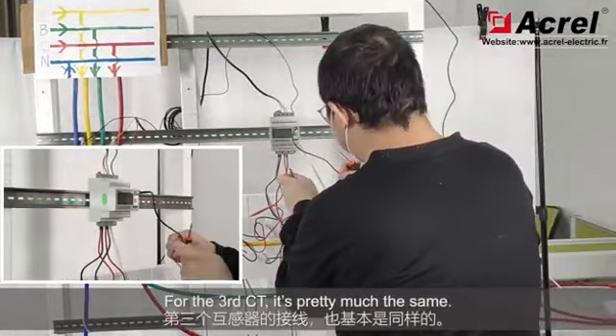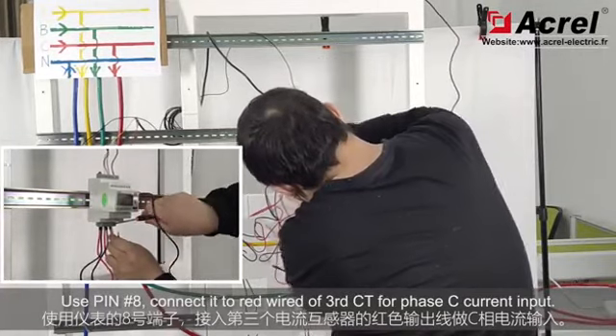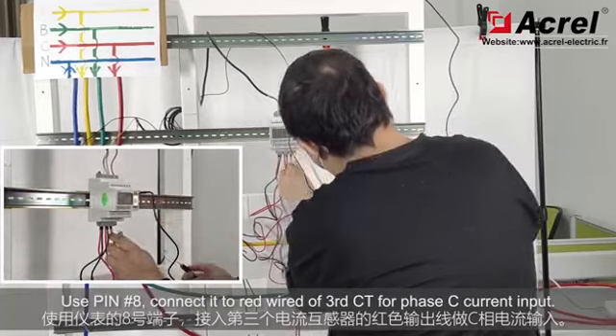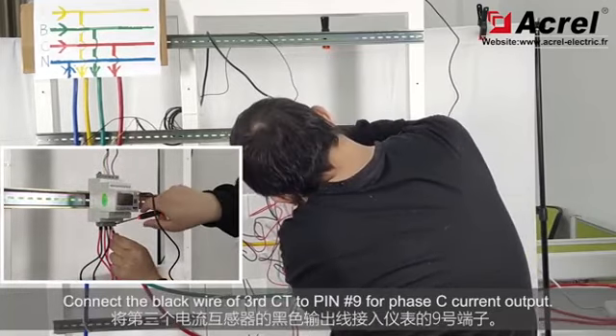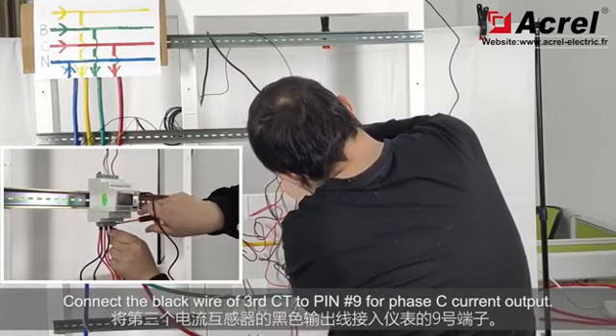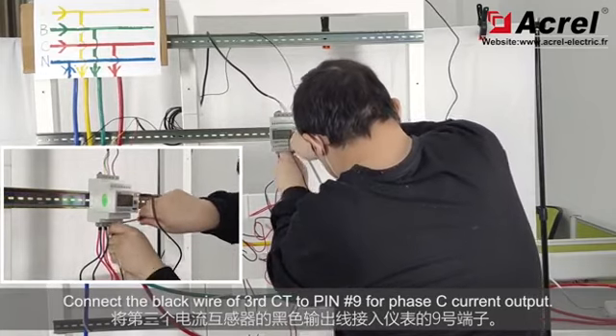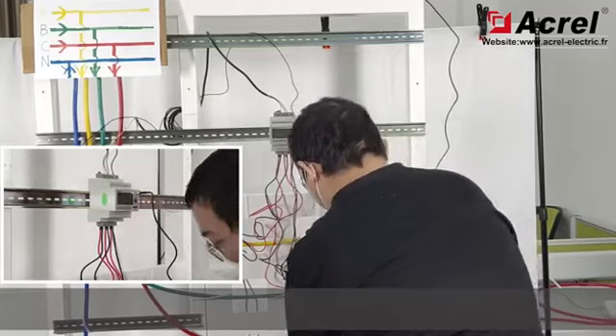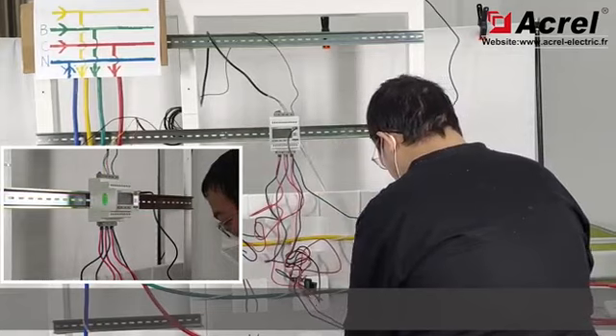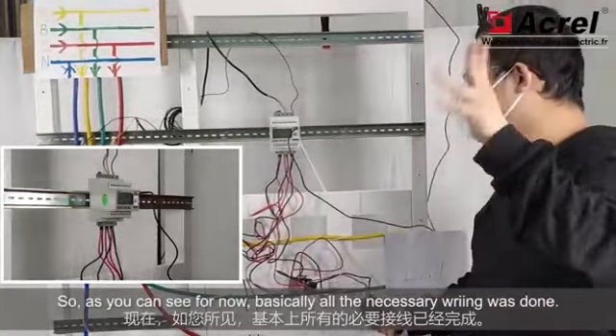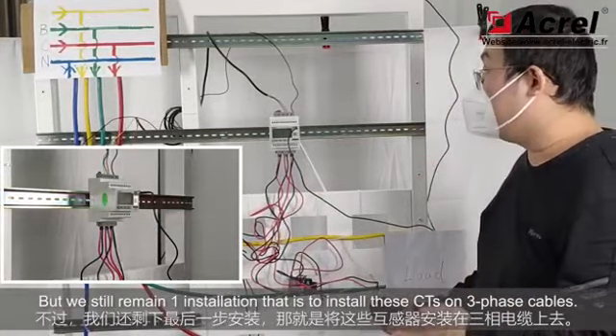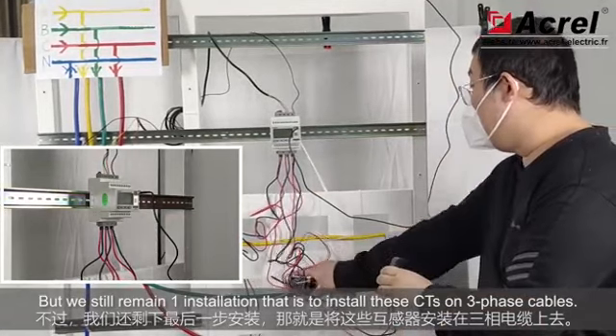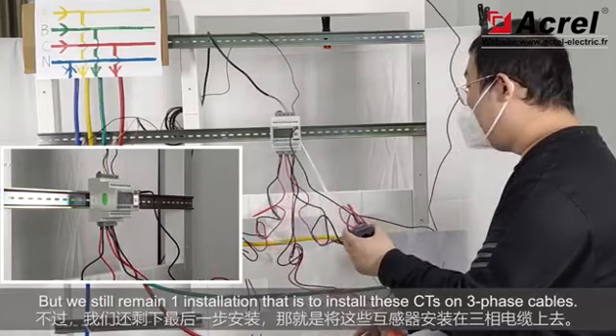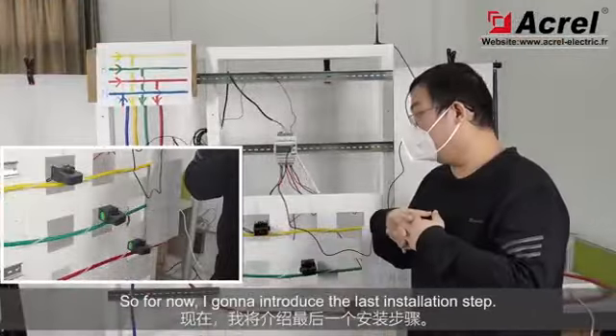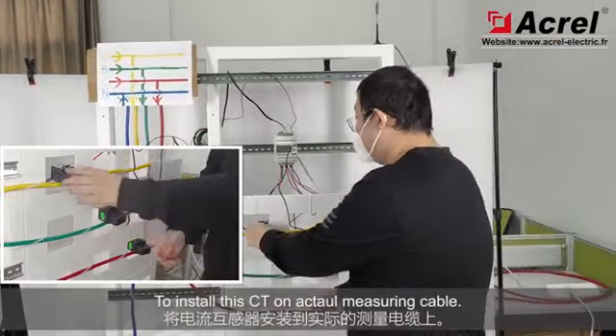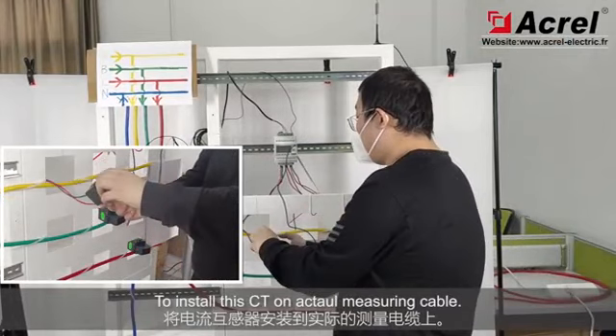For the third CT is pretty much the same. Use pin 8 connect to red wire of the CT for phase C current input. Connect the black wire of CT to pin 9 for phase C current output. So as you can see for now, basically all the wiring was done, but we still remain one installation, that is to install the CT on the three-phase current cable respectively. So for now, I'm gonna introduce the last installation step to install this CT on the actual measuring cable.